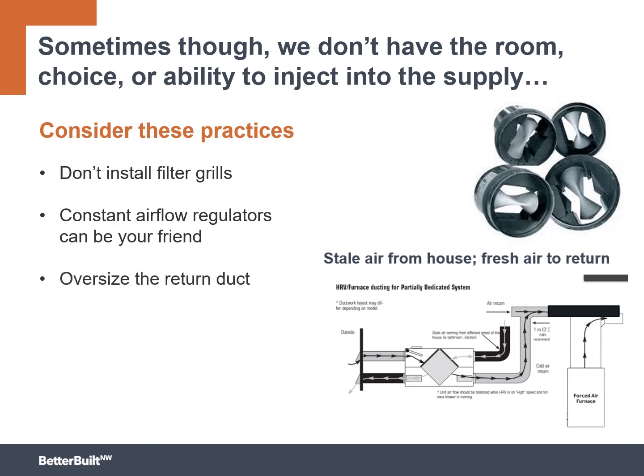And finally, you should be doing Manual J, D, S, and T for your central systems. You might want to oversize the return duct portion of your central air handler. It's almost never a bad idea to do that, but particularly when you're doing this. Again, if you have a slightly larger return duct component of your central air handler, the negative pressures inside of it will be lower, because the same volume of air through a larger duct means a lower, or less negative, pressure. You combine all three of these practices and you could actually connect to the return side without too much of a penalty.